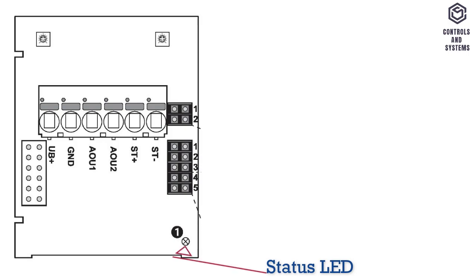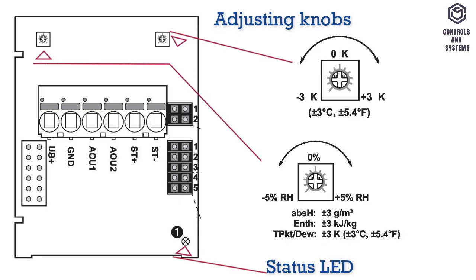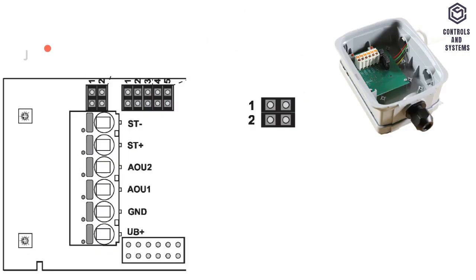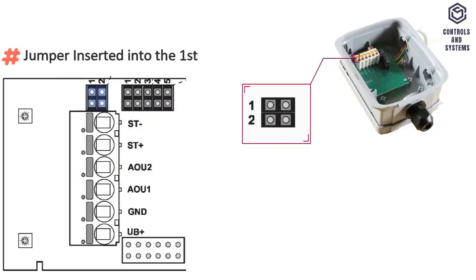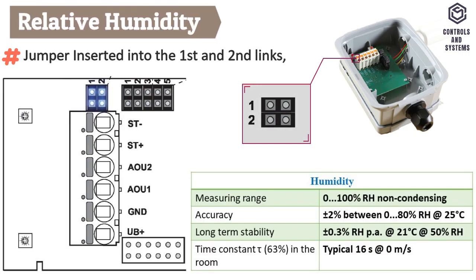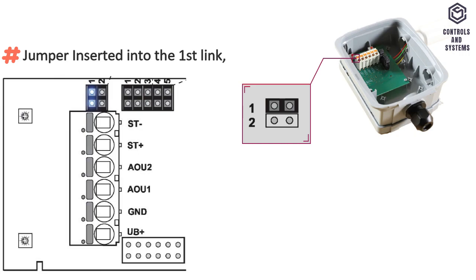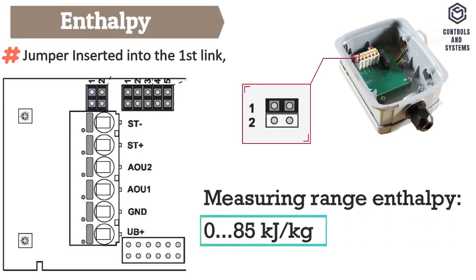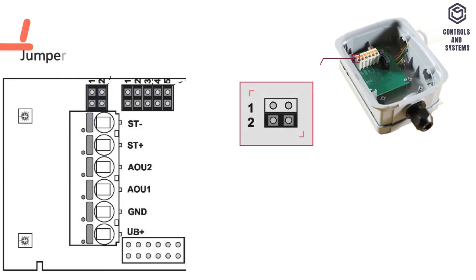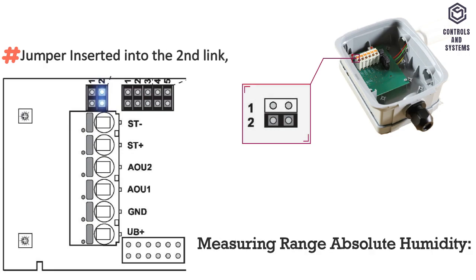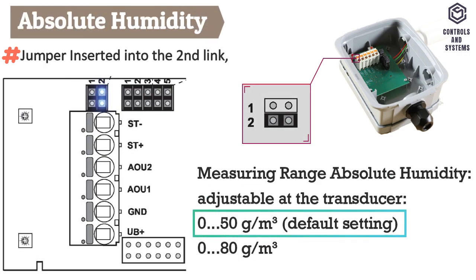This is the status LED. These two adjusting knobs are used to calibrate the humidity and temperature values. If a jumper is inserted in the first and second terminals, the sensor will show the relative humidity value. Humidity measuring range and specifications are shown in the table. If a jumper is inserted in the first terminal, the sensor will show the enthalpy value. If a jumper is inserted in the second terminal, the sensor will show the absolute humidity value.